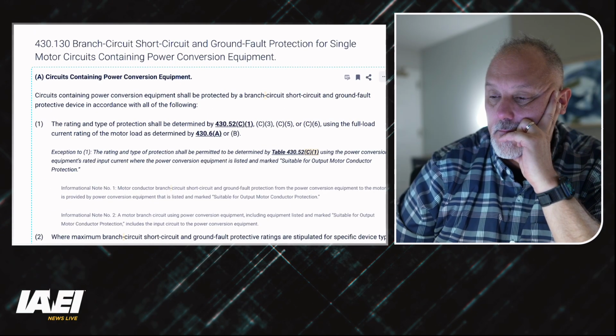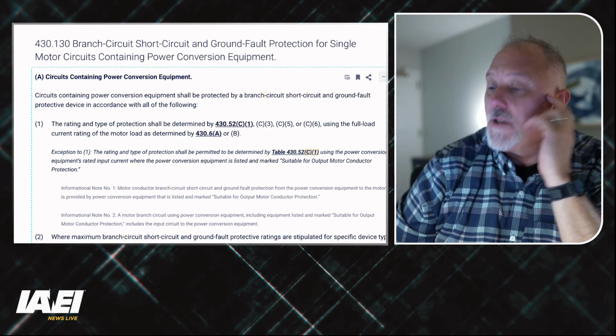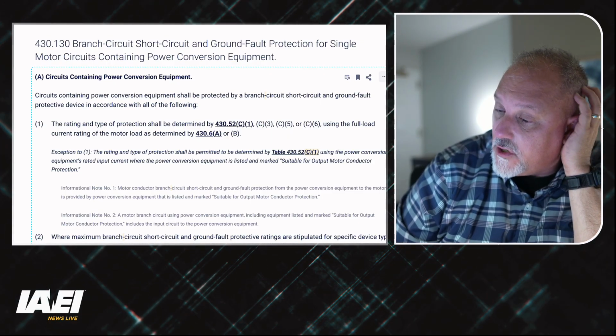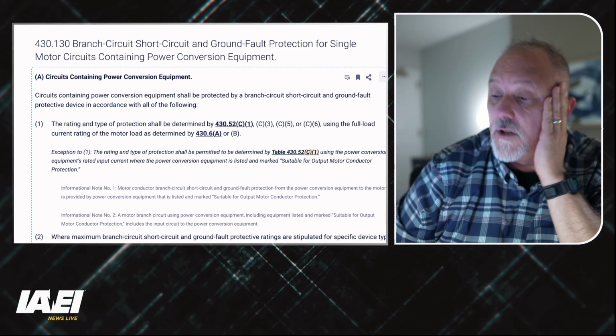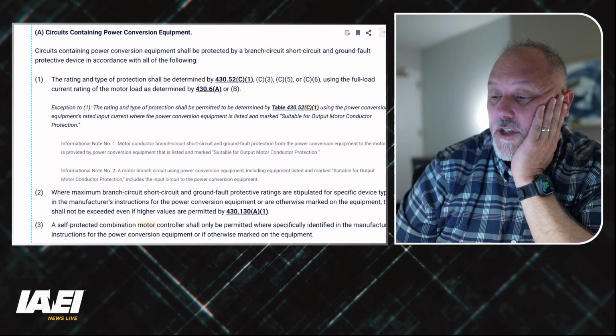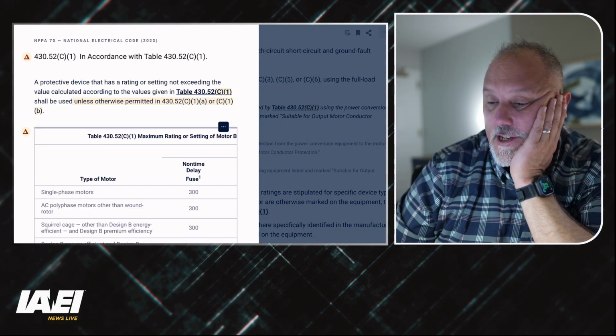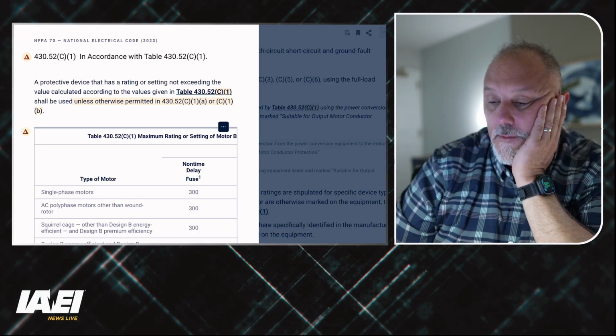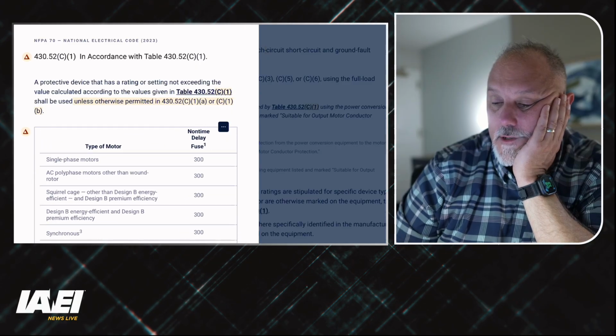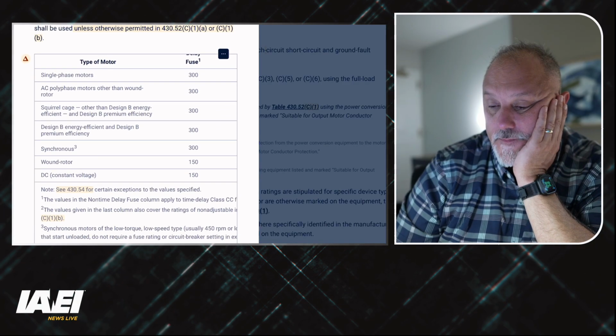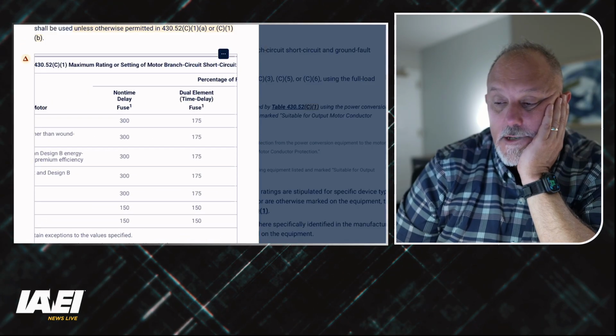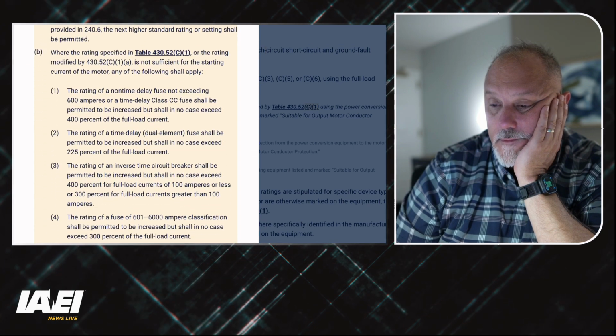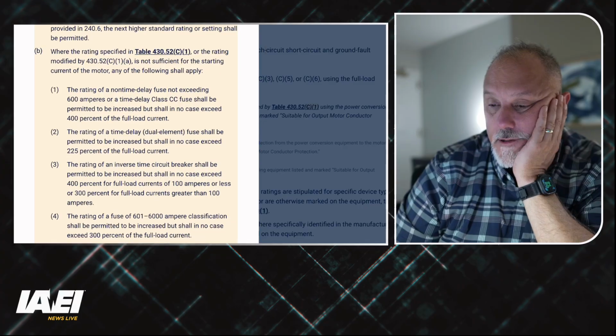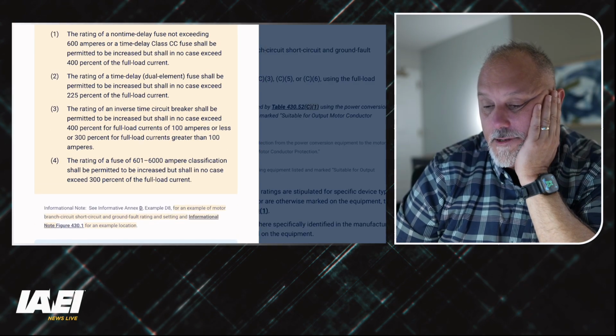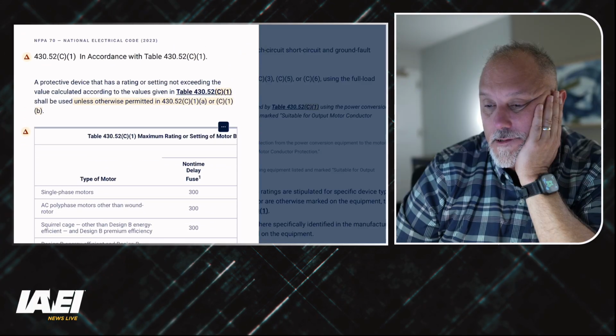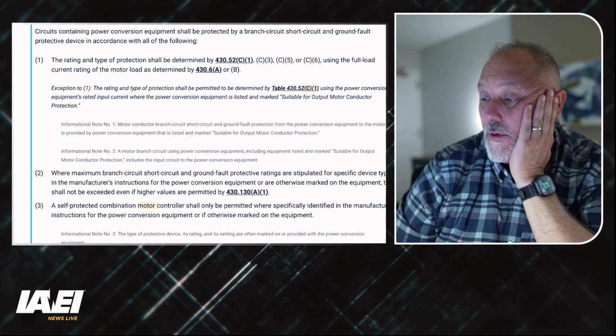language: branch circuit, short circuit, ground fault for single motor circuits. Circuits containing power conversion equipment shall be protected by a branch circuit, short circuit, and ground fault protective device in accordance with all of the following. 1. The rating and type of the protection shall be determined by 430.52(C)(1), (3), or (5). That's your single phase. Oh, wait a second. This is based on the motor. It says (C)(3)... that's (C)(1), (C)(1), (C)(3), (C)(5), or (C)(6).